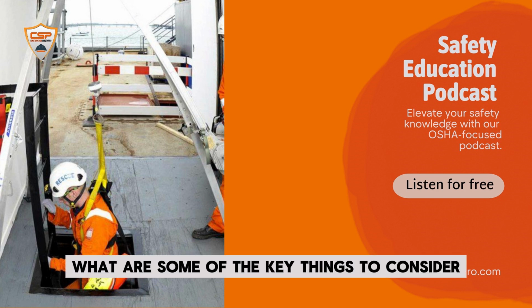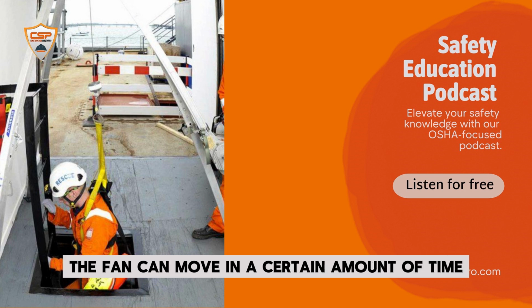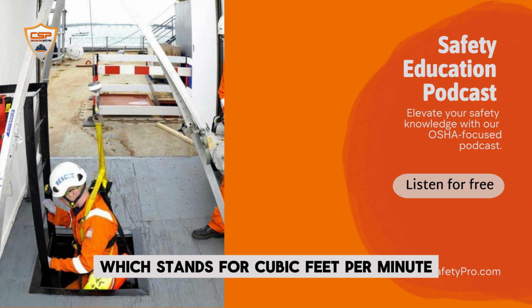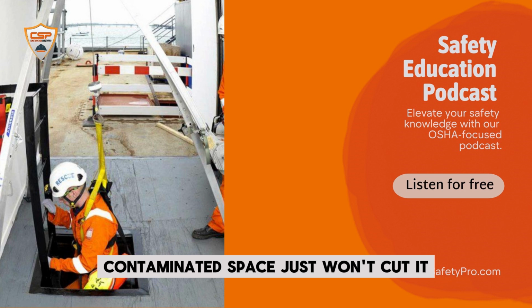What are some of the key things to consider when picking out those fans? Well, the first thing is flow rate, which basically tells you how much air the fan can move in a certain amount of time. It's measured in CFM, which stands for cubic feet per minute, or m³/h, which is cubic meters per hour. And you need to get a fan that's powerful enough for the size of the space and how bad the hazards are. A small fan in a big contaminated space just won't cut it.